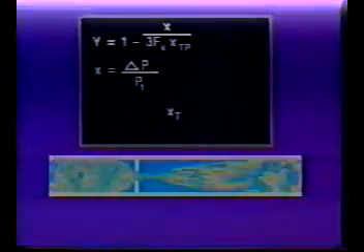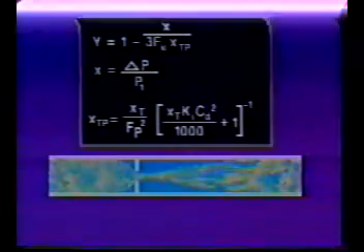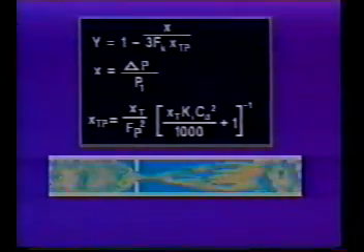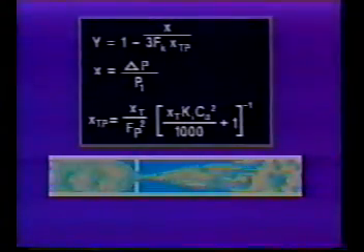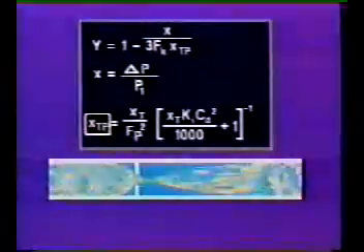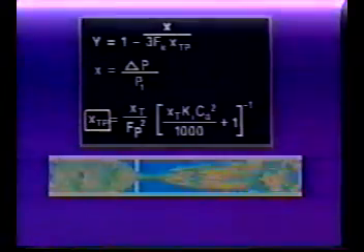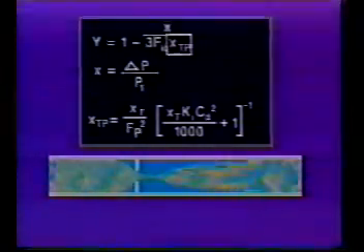To compensate for changes that are introduced by the use of inlet piping reducers, this formula must be solved. Outlet reducers do not affect the value of X sub T. When inlet piping reducers are used, the modified value of X sub T becomes this factor, X sub TP. As you can see, this factor is also used to determine the value of Y.